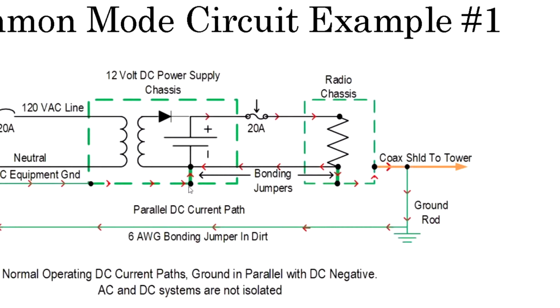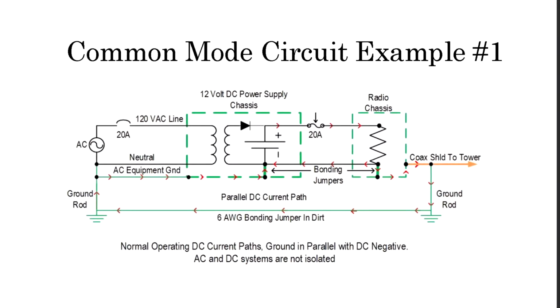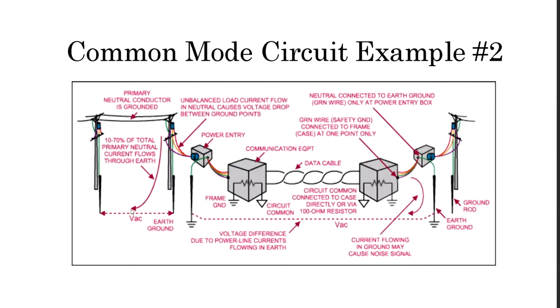We've done it twice. So we're forcing some of the current, we're taking current off of the return, our planned return path, the black wire from the radio back to the power supply, the one we know about. But with these jumpers in there, it's also forcing some common mode current to flow. So this is just an example of how it can happen. There are other methods and mechanisms that cause us the real headaches, and we're going to take a look at some of those.